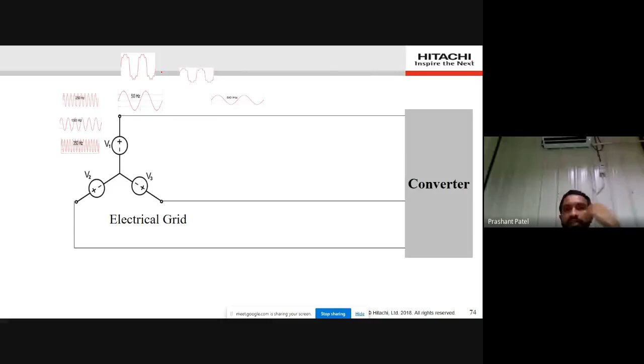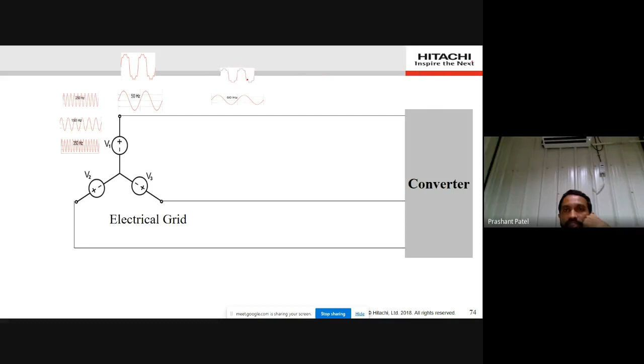This is a sinusoidal voltage, and here the grid voltage is like this. The harmonic components have a phase difference because we are not generating any harmonics through the converter, we are generating only the fundamental waveform. So the harmonic current also flows from the grid to the converter, and unnecessarily this current may exceed the criteria of less than 3% current THD.